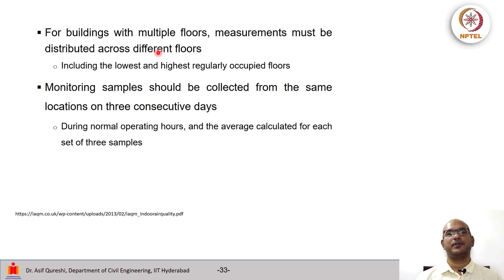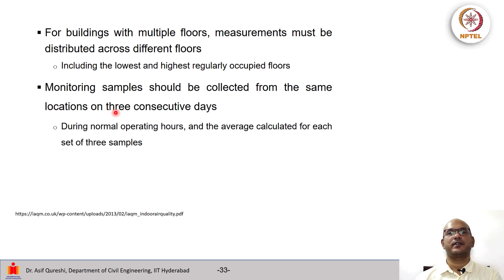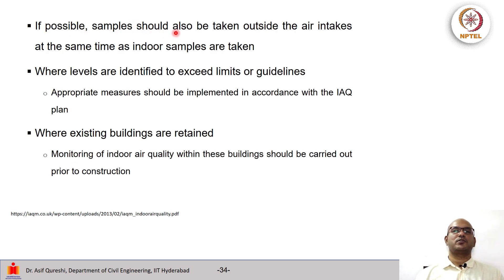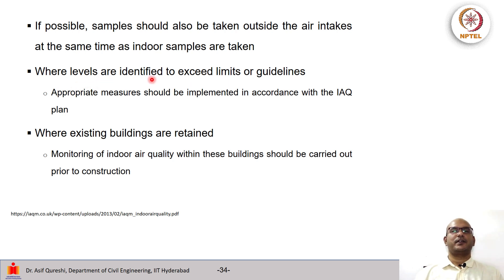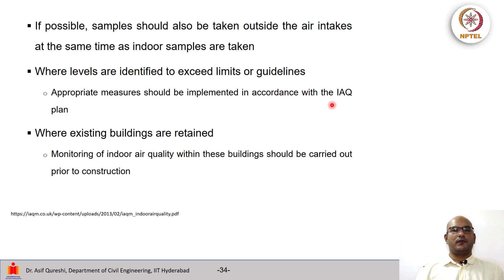For buildings with multiple floors, measurements must be distributed across different floors, including the lowest and highest regularly occupied floors. Monitoring samples should be collected from the same locations on 3 consecutive days during normal operating hours and the average calculated for each set of 3 samples. If possible, samples should also be taken outside the air intakes at the same time as indoor samples, so that one can match the indoor to outdoor relation. Where levels are identified to exceed limits or guidelines, appropriate measures should be implemented in accordance with the IAQ plan. Where existing buildings are retained, monitoring of indoor air quality should be carried out before construction starts.